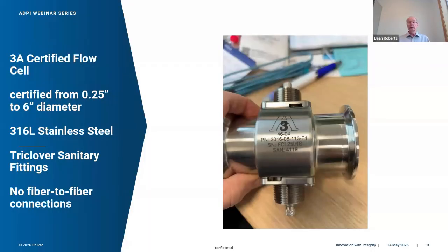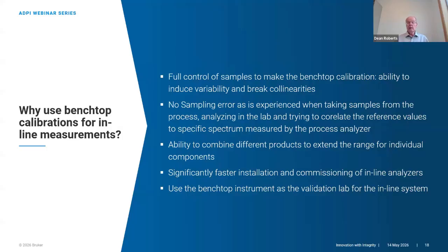And by using the Benchtop instrument as a validation source, we can get those results much, much more quickly than using the reference method. So we do one measurement that takes 30 seconds rather than 5 measurements for the protein, the fat, the total solids, the lactose, and we can get it done much faster.